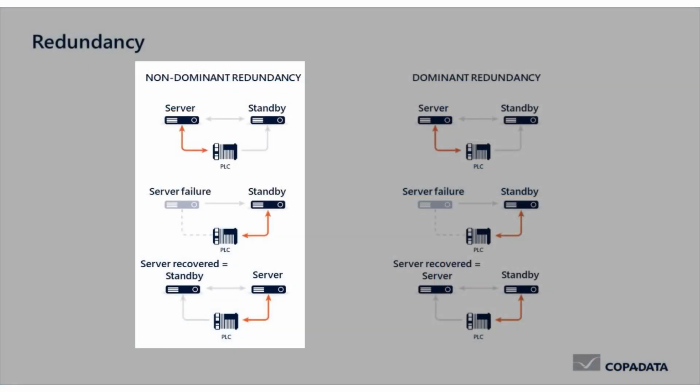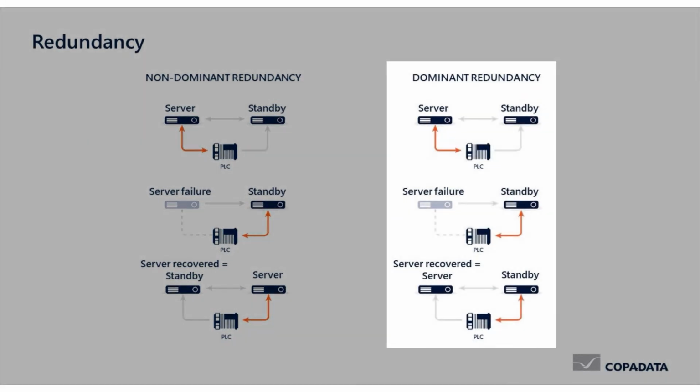The non-dominant redundancy demonstrated in this example is the default redundancy mode in zenon, as it minimizes the amount of redundancy switches and is recommended for systems where both servers are equal, have equal performance and resources, and have access to all devices. By contrast, if the dominant redundancy mode is selected, one computer is defined as primary server and a second computer as standby.